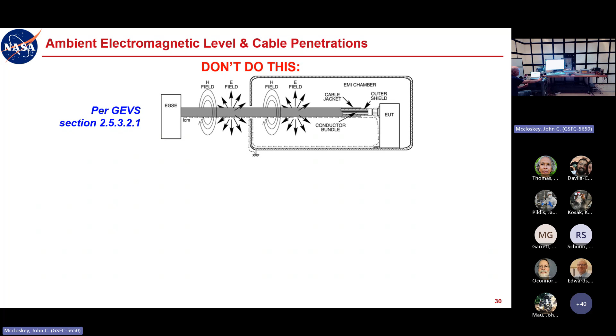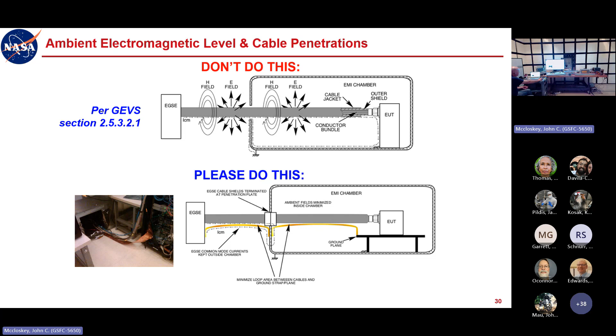We terminate cable shields right at the penetration plate. And this is the reason why we tell you to do that. The common mode currents, at least ideally, theoretically, will stop at the chamber, and you help them along as much as possible if you provide a nice low impedance path back to the source, because currents will go back to the source. They must. Nature says so. Kirchhoff was just the messenger. Nature says the currents must go back to the source. And if you provide a low impedance path for those currents to get back to the source, that's the path that they will want to take. And it stops them at the wall, and they will not go into the chamber and affect your ambient measurement.